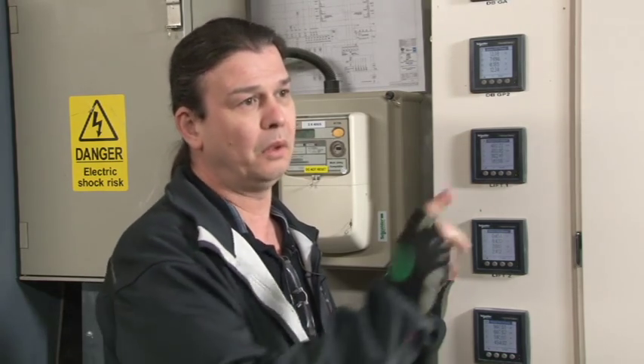Adjacent to every piece of equipment is a means of isolation. So the lifts have an isolator. The AOVs have an isolator. If you're doing a maintenance task on that piece of equipment, you expect to find an isolator within 1 metre, as the crow flies, as it were, and that's your safe point of isolation. You isolate from there and you padlock off, and that's you safe to work on that piece of equipment.